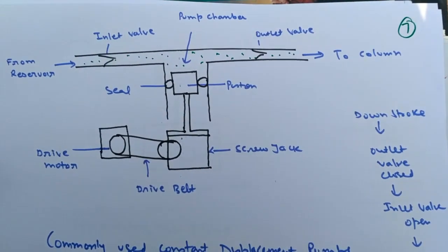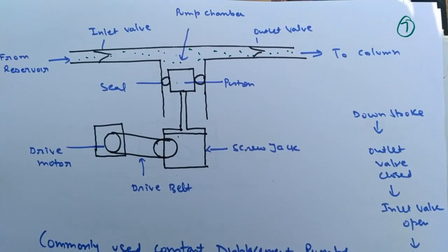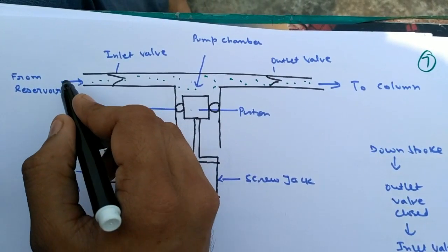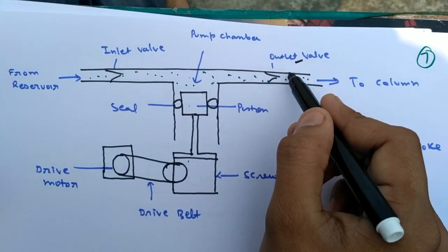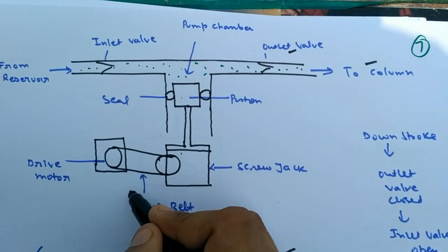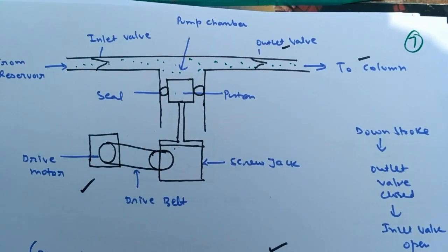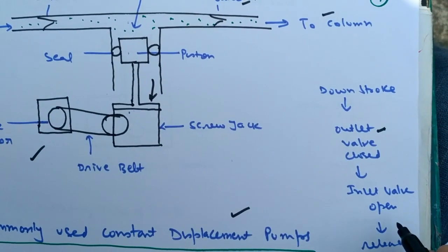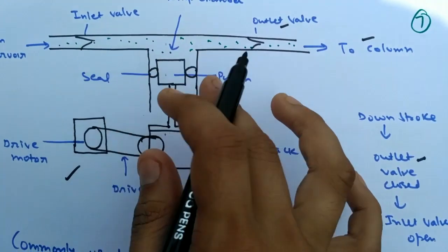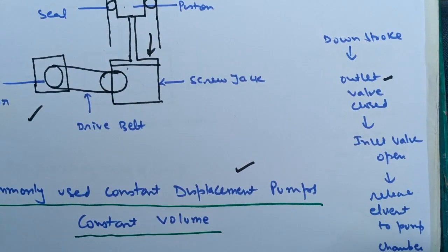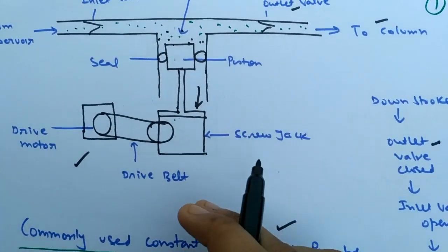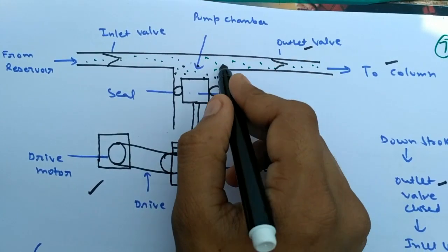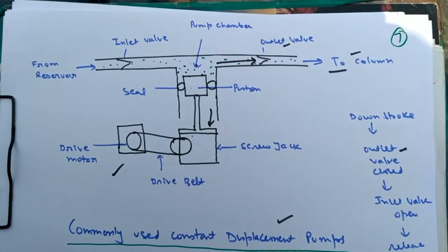The pumping system pumps the solvent into the column. In the constant displacement pump, there is an inlet connected to the solvent reservoir and an outlet sending solvent to the column. A piston system is driven by a motor with a pulley and belt. On the downstroke, the outlet valve closes and the inlet valve opens, allowing entry of solvent to fill the pump chamber. On the upstroke, the reverse occurs — inlet closes, outlet opens — and the collected solvent is sent to the column.